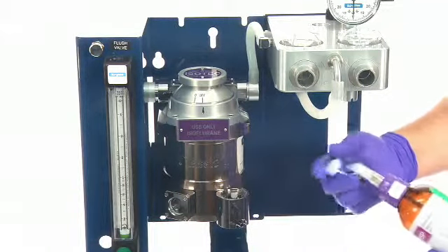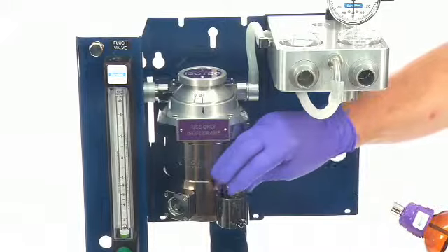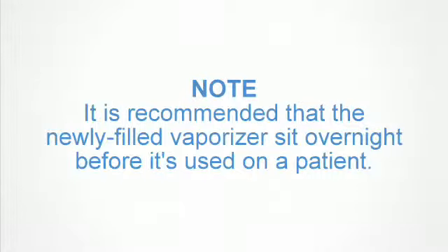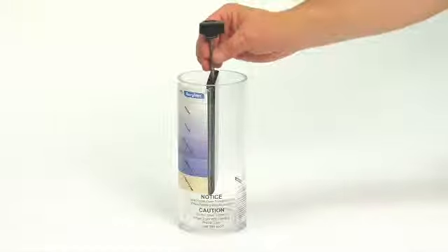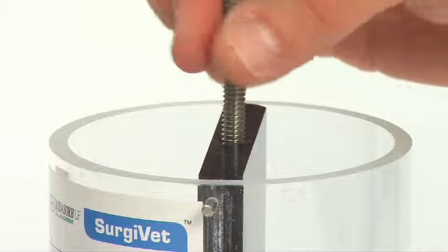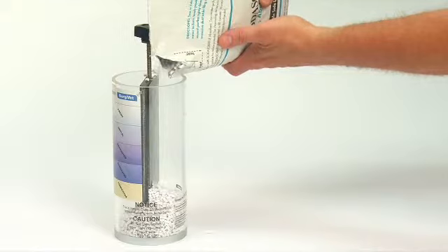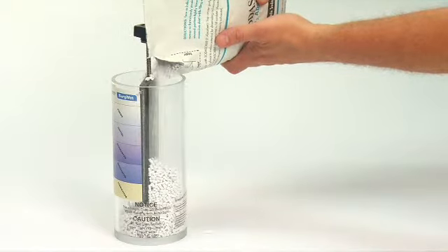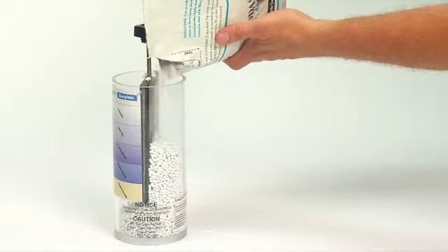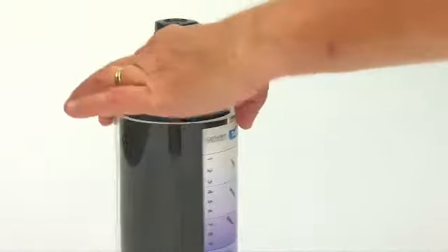A fill adapter will help reduce spills. It is recommended that the newly filled vaporizer sit overnight before it is used on a patient. This allows the internal wick to adequately absorb the agent to ensure proper function of the vaporizer. Place the draw knob screw into the screw port of the black divider. This prevents granules and/or dust from entering the threads and causing an obstruction of a proper seal.